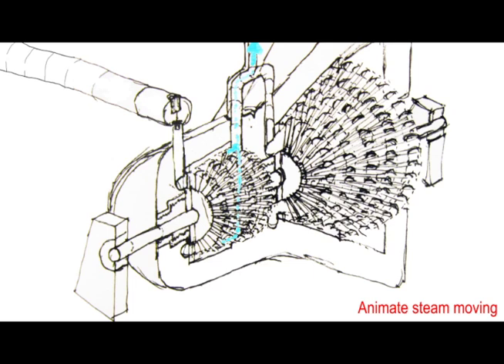After the steam has passed through the first section of the turbine, some of the steam is removed from the turbine at 90 pounds per square inch and 500 degrees Fahrenheit through the steam extraction valves. This steam is then used to heat university buildings or power university chillers, which air condition the buildings on campus.